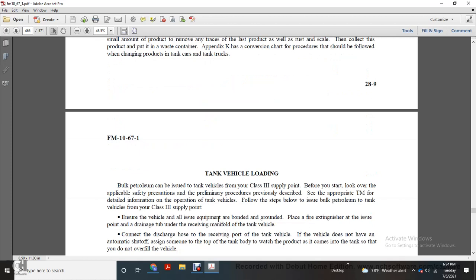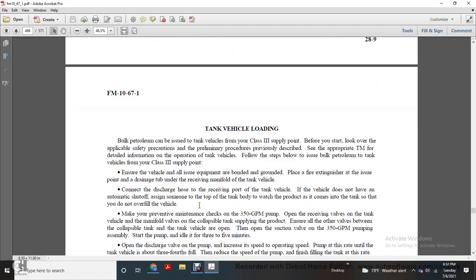Tank vehicle loading. Bulk petroleum can be issued into a tank vehicle at the Class 3 supply point. Before you start, look over the applicable safety precautions. Perform the preliminary steps previously described and consult the appropriate equipment manual for detailed information on operation of the tank vehicle. Follow the steps below for bulk petroleum into the tank vehicle at the Class 3 supply point. Ensure the vehicle is grounded at the issue equipment. Connect the bonding and grounding. Position the discharge hose to the receiver manifold of the tank vehicle. If the vehicle does not have an automatic shutoff, assign someone to the top of the tank to watch the product as it comes into the tank so you do not overfill the vehicle.